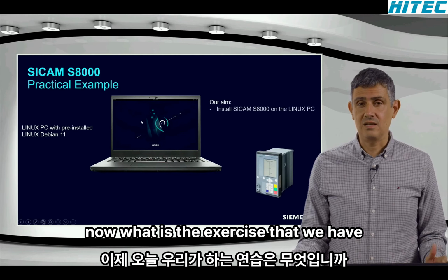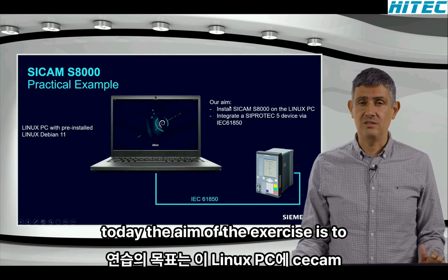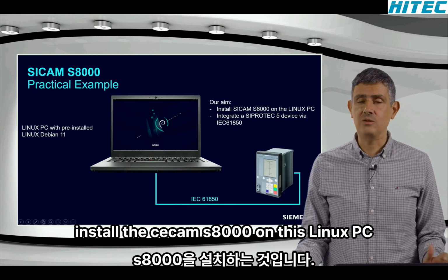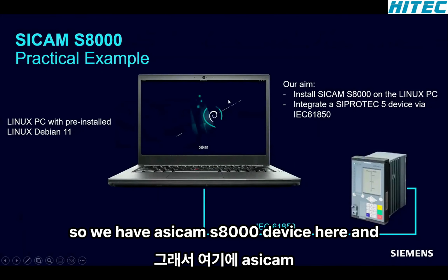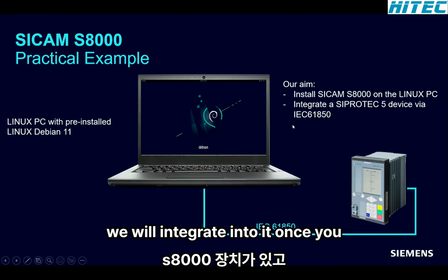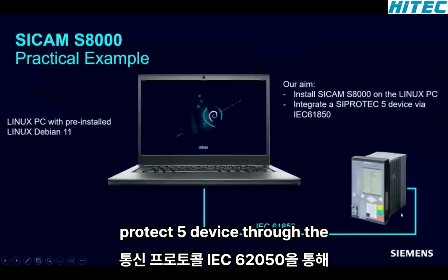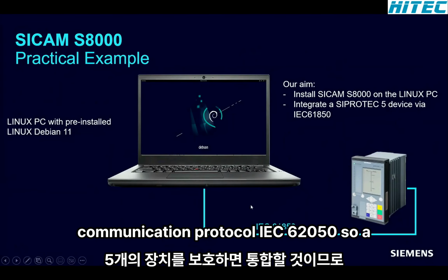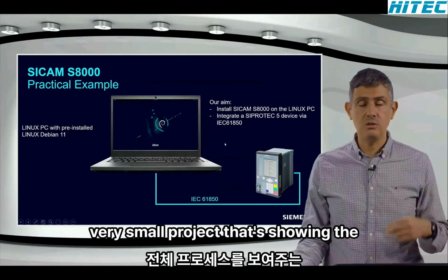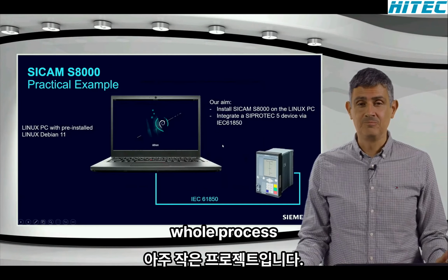Now, what is the exercise that we have today? The aim of the exercise is to install the Sicam S8000 on this Linux PC. So we have a Sicam S8000 device here, and we will integrate into it one SIPROTEC 5 device through the communication protocol IEC 61850. So a very small project that's showing the whole process.